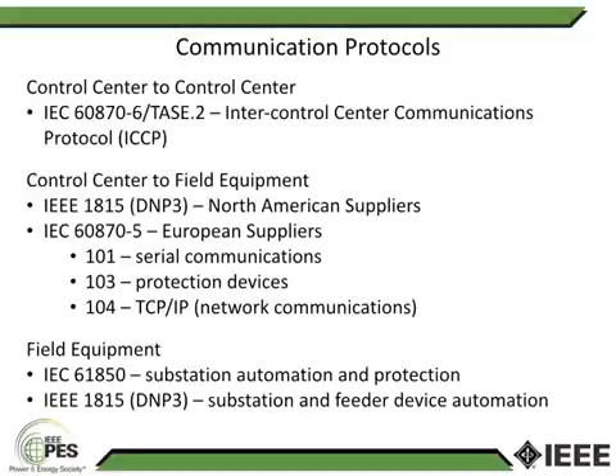From the control center down to the field equipment, there are really two standards used. One is DNP3, Distributed Network Protocol 3, used in North America, now with an IEEE designation of 1815. The other is IEC 870-5, used with European suppliers: 101 is serial communications, 104 is network, and 103 is for protection devices.